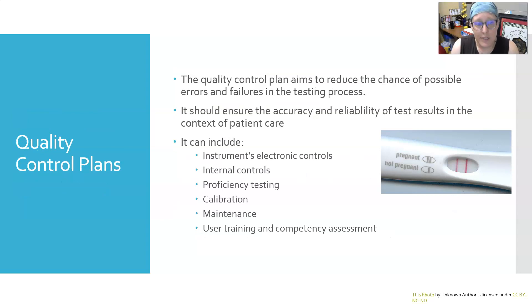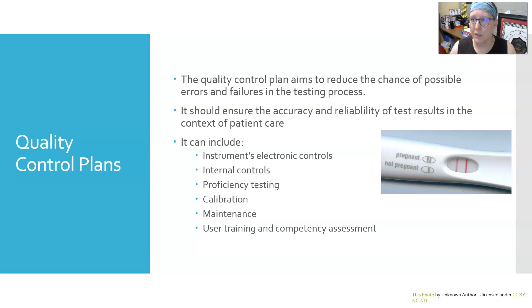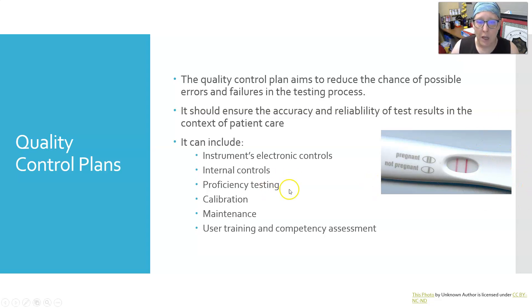Quality control plans aim to reduce the chance of possible errors and failures in the testing process. They should ensure the accuracy and reliability of test results in the context of patient care. A QC plan can include an instrument's electronic controls, internal controls — which are usually built into the test. For example, a pregnancy test where two lines means pregnant, one line means non-pregnant, and that one line is the internal quality control. If you have no lines, it's an invalid test. QC plans can also include proficiency testing, calibration, maintenance, and user training and competency assessment.